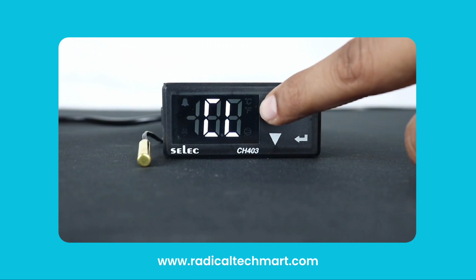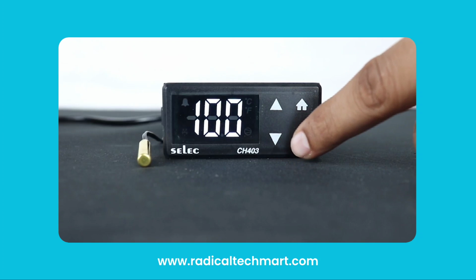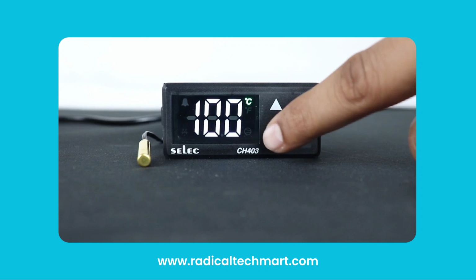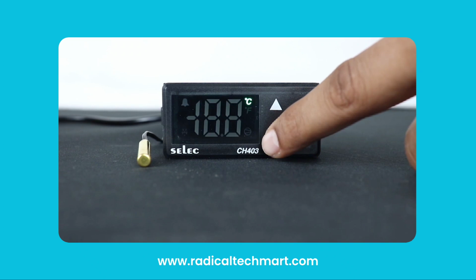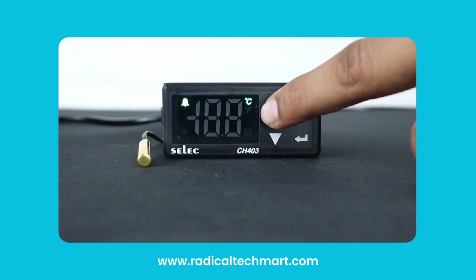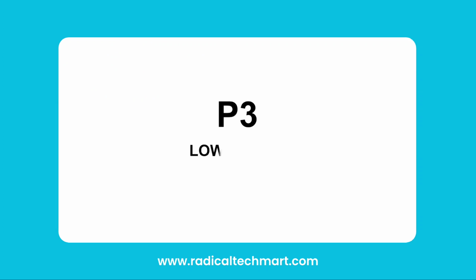Now, to the next parameter, which is P2 denoting high alarm. Press the Enter key to edit, and the up and down keys to increment and decrement the value respectively. Here, we are taking 20 degrees Celsius temperature as high alarm. To save the value, press the Enter key once. Now, proceed to P3 to set the low alarm for the controller.